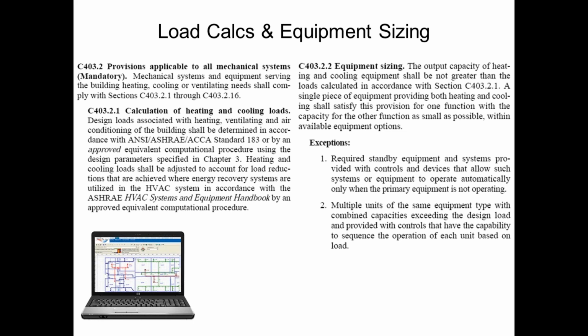Now, it does say that obviously with a package unit, you're not going to have identical heating and cooling loads that match up with every manufacturer's scenario. So you are allowed to round up to the nearest heating or cooling size to try to match with the other one, right? So if you need 7.5 tons of cooling with, whatever, I don't even know, 200,000 BTUs of heating, but you have to get one that has 220,000 BTUs of heating, you can do that to get the cooling to work out right and vice versa. So you are allowed a little bit of flexibility there, but you can't just start upsizing things and going up to the next whole random size kind of thing.